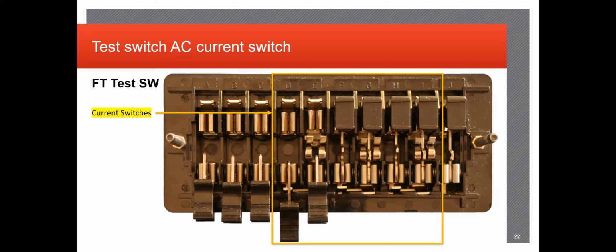So the reason for these shorting bars is if somehow accidentally or even while testing, I mean, you can damage the relay itself if you have an open CT during testing, but the shorting bar allows a safe path for the current to go if the switch was to be open. Pretty much these shorting bars just lead straight to ground. So again, you don't want to apply a steady, long, strenuous amount of current on these open CTs because you don't want a circulating ground current either associated with this. But yeah, it's pretty much a safety measure, and you can easily identify them when you're out in the field.